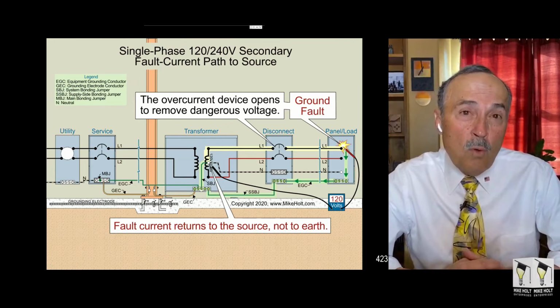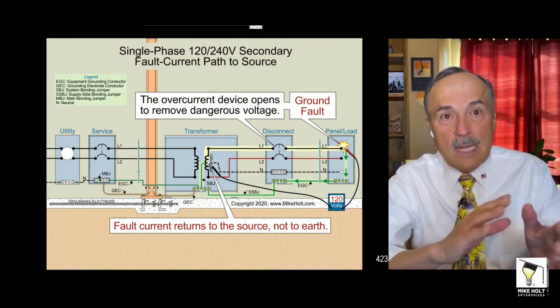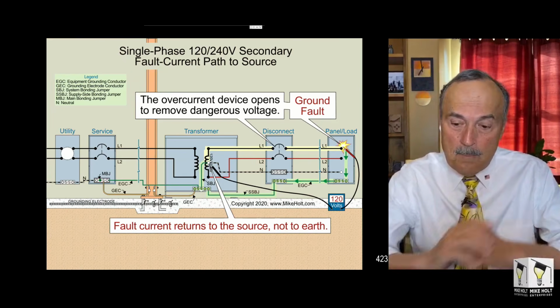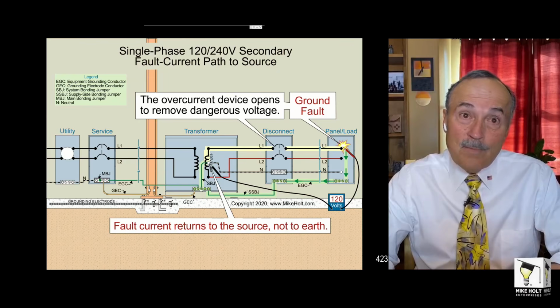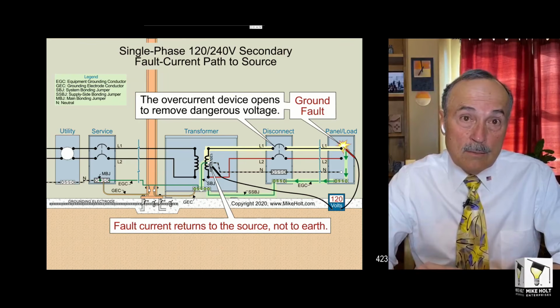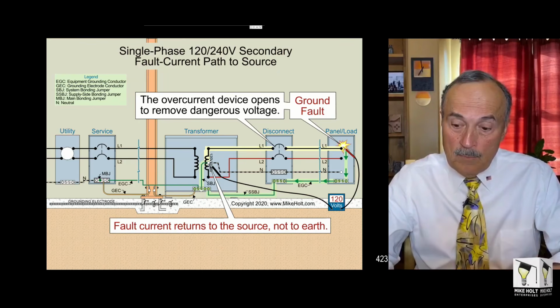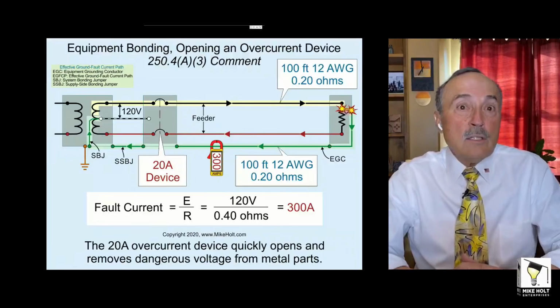And what does it do to the overcurrent device? Probably opens it up in about 0.03 seconds, depending upon the type of overcurrent protection device that you have. Guess what? Fault current is not going to ground, guys. So forget about all these ground rods you guys are driving. Okay? Now let's just look at it again.